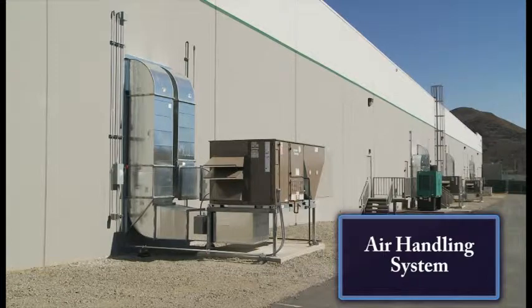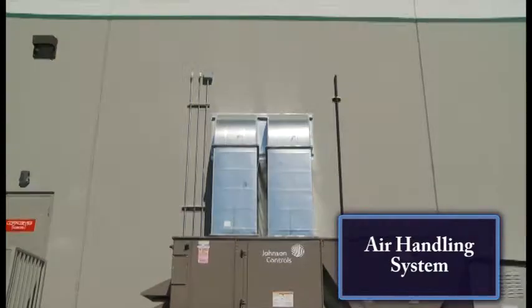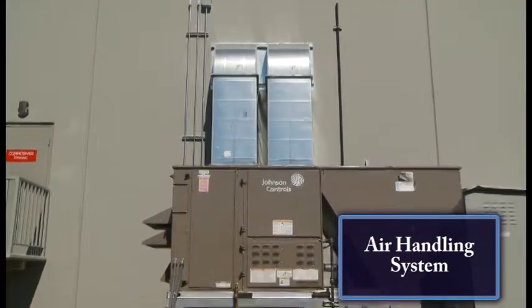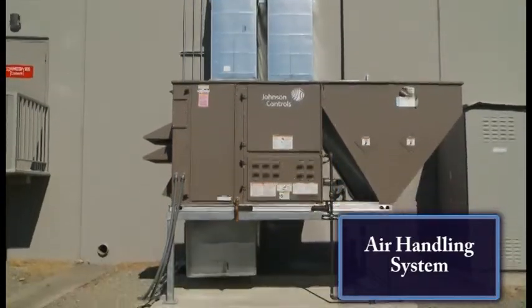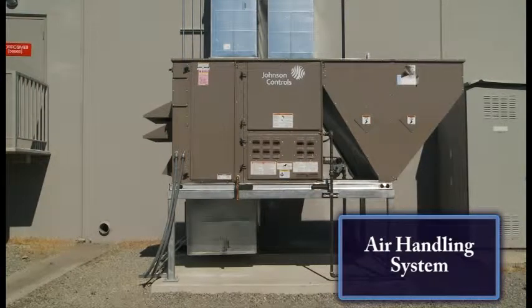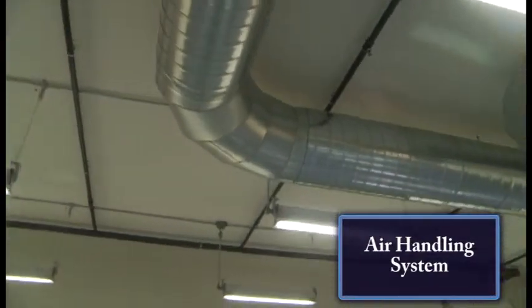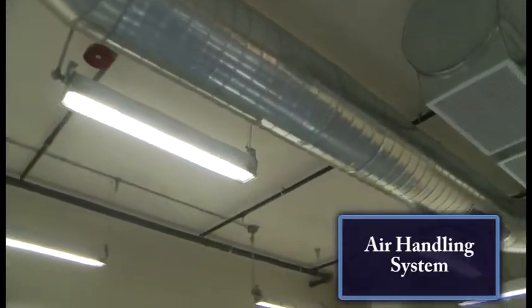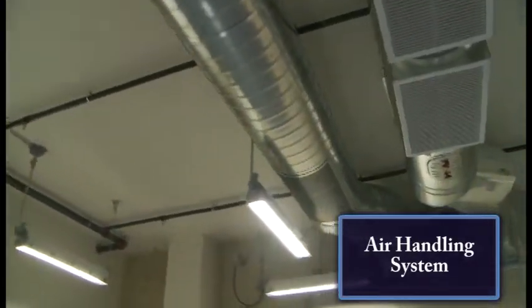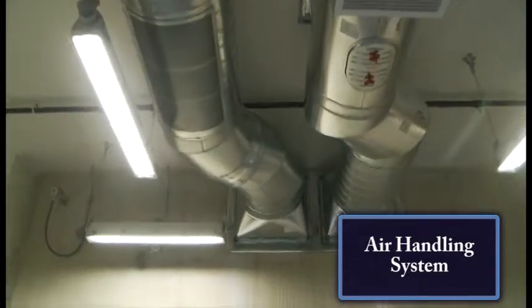Each individual hazard room is provided with a dedicated air handling ground-mounted unit. Air is withdrawn from the space served by the same unit and exhausted at a rate of 6 air changes per hour. Air is completely replaced in the affected space every 10 minutes. All air handling equipment will automatically be de-energized in the event of a fire.